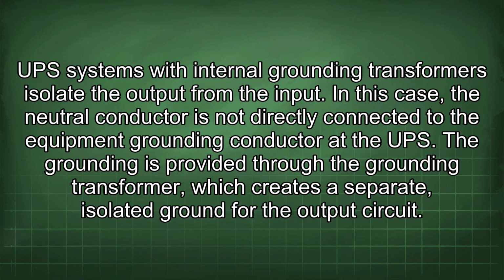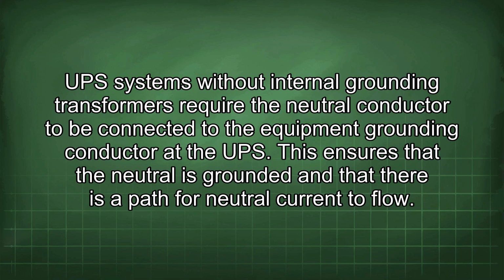UPS systems with internal grounding transformers isolate the output from the input. In this case, the neutral conductor is not directly connected to the equipment grounding conductor at the UPS. The grounding is provided through the grounding transformer, which creates a separate, isolated ground for the output circuit. UPS systems without internal grounding transformers require the neutral conductor to be connected to the equipment grounding conductor at the UPS.